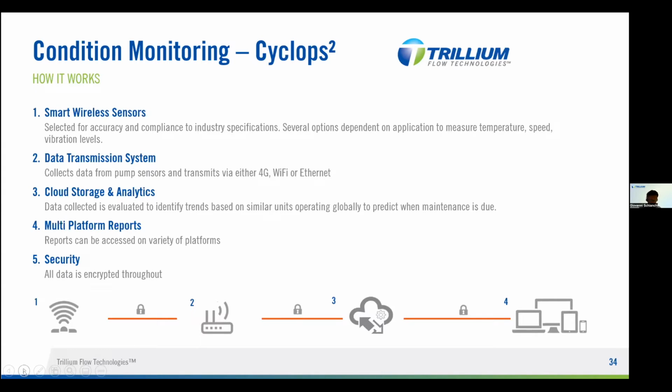Sensors providing several types of measurements. Sensors are not requiring large space. Normally, the diameter is 40 millimeters, so very small. And each sensor is providing more information. To give an example, one multi-purpose sensor typically provides a signal of temperature and vibration and 3 signals of vibration along 3 axes. So a very compact solution.